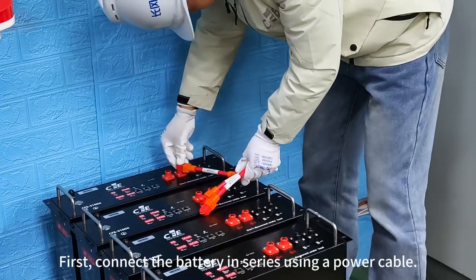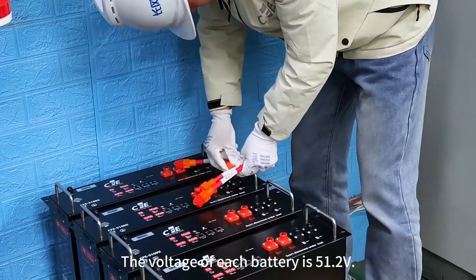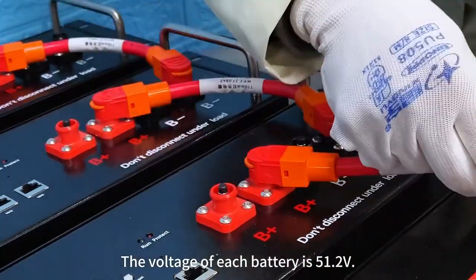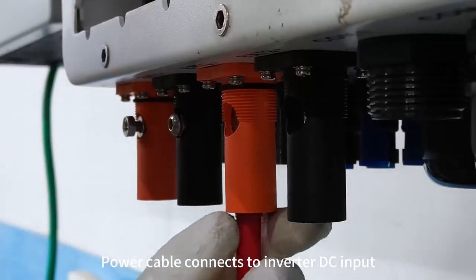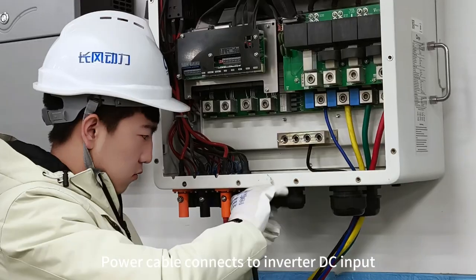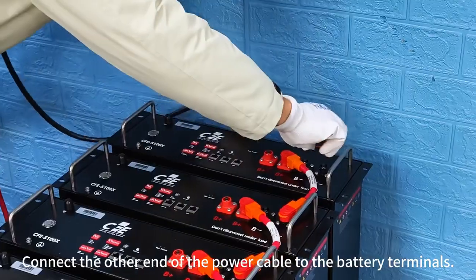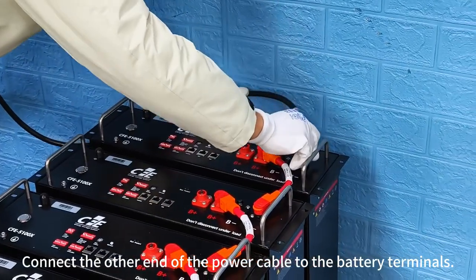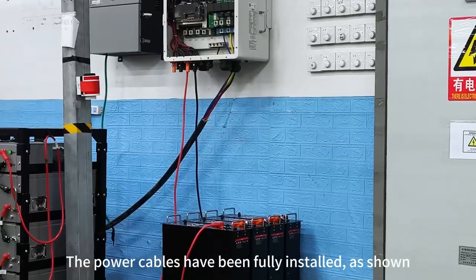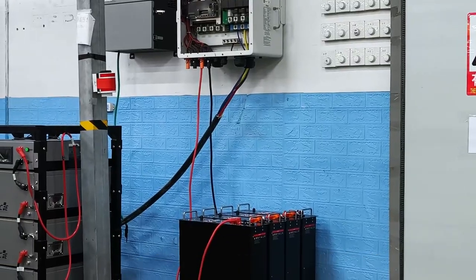First, connect the battery in series using a power cable. The voltage of each battery is 51.2 volts. The power cable connects to the inverter's DC input, with the other end connected to the battery terminals. The power cables have now been fully installed, as shown.